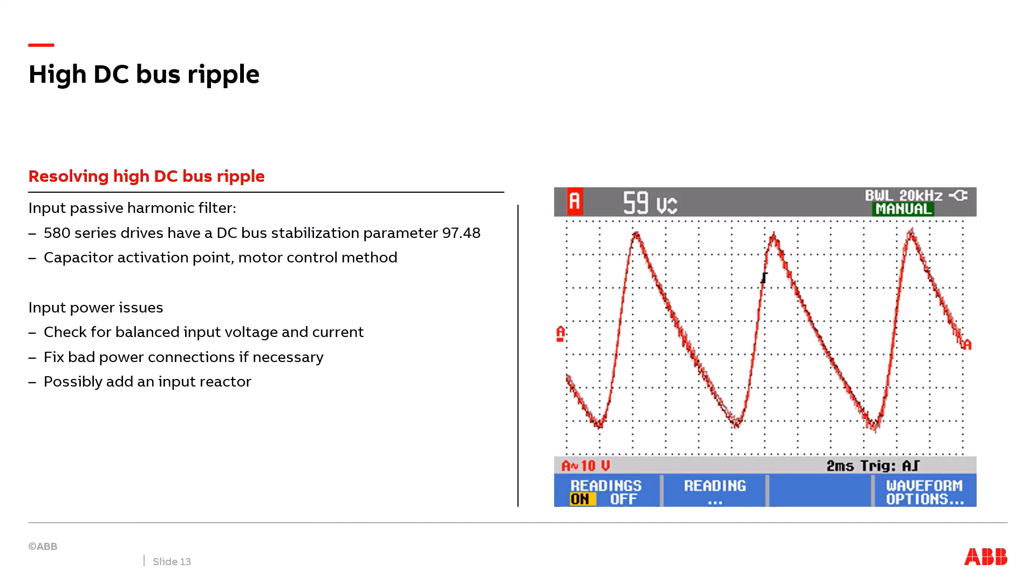Now if your DC bus oscillation is caused by input power issues check for balanced input voltage and current. Make sure everything's balanced there. If you have bad connections make sure you adjust those connections. Maybe you have a loose connection that could be causing a high DC bus ripple. If all the connections look good and you maybe just have pure unbalanced input voltage causing imbalanced input current to the drive possibly adding an input line reactor in front of the VFD will help resolve the high peak to peak voltage DC bus ripple.